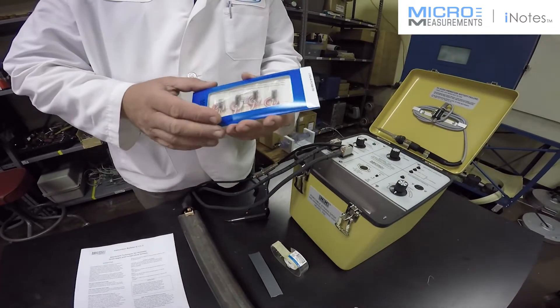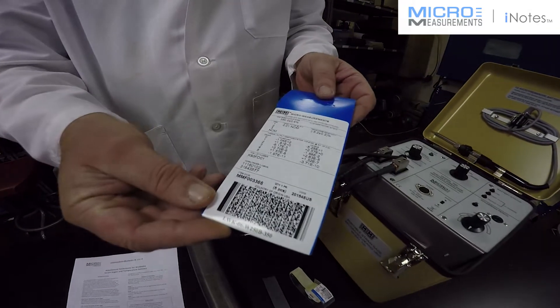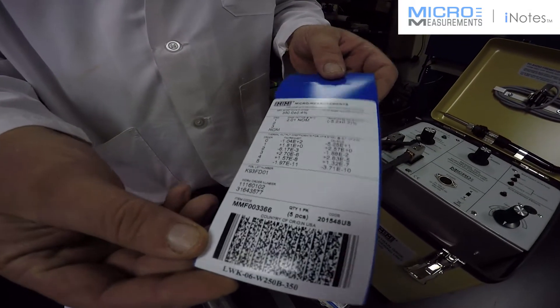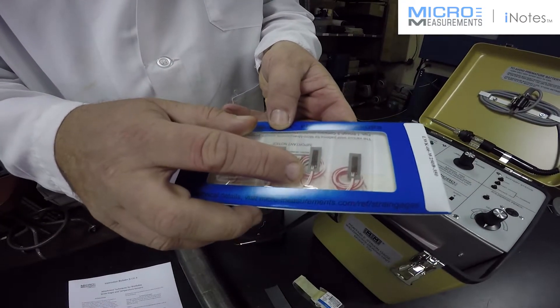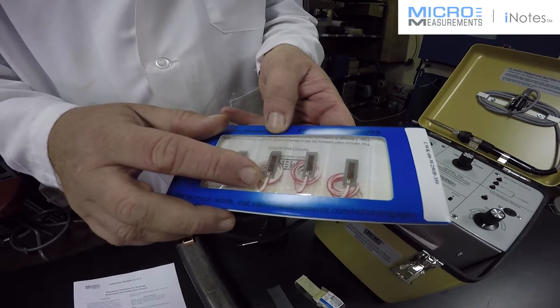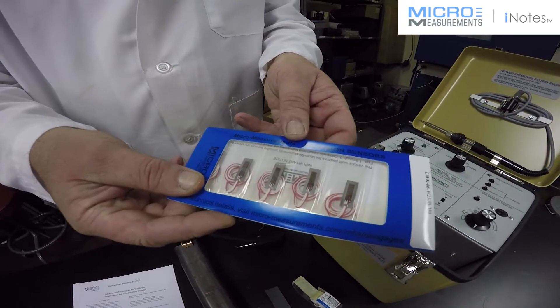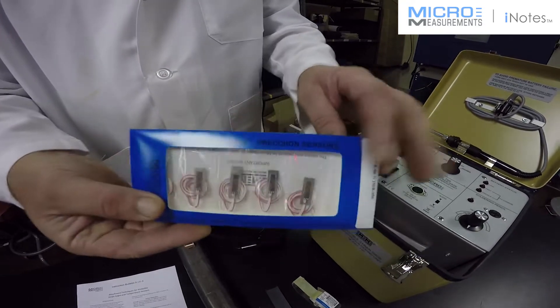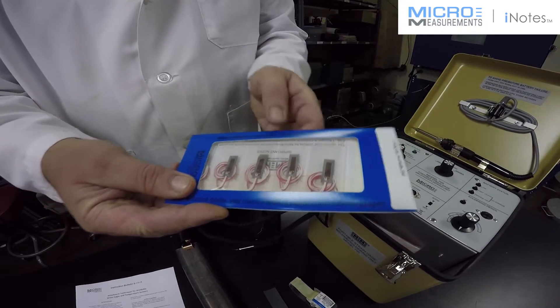Let me talk first about the strain gauges. This particular series that I have here is LWK, and to show you the back here, these are pre-cabled gauges. They have about 10 inches of a Teflon insulated cable. They're good up to 500 degrees Fahrenheit, and you can weld these to stainless steel, steel, even titanium — those are probably the most common uses for this type of weldable strain gauge.